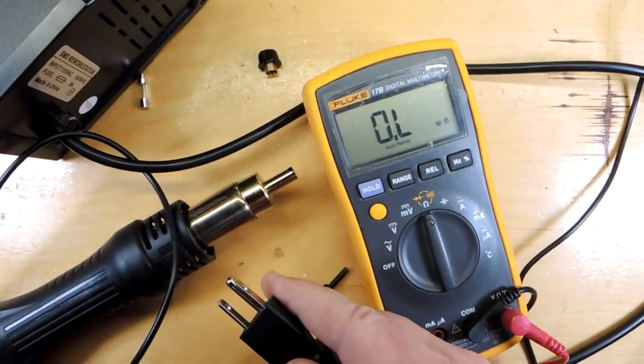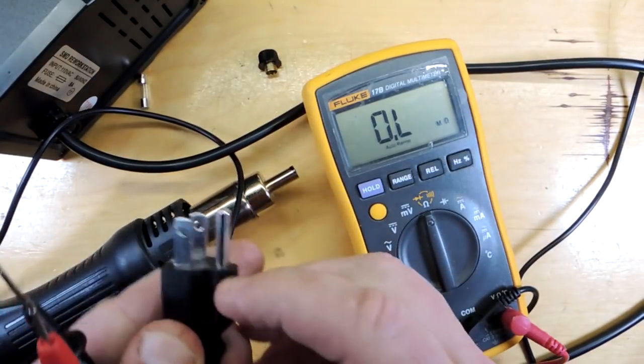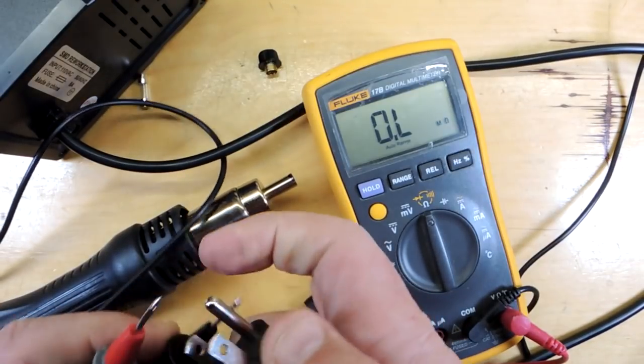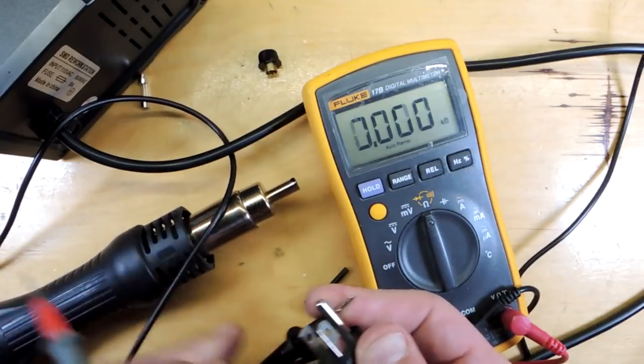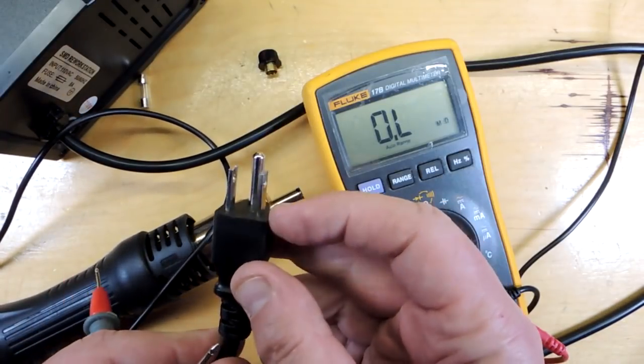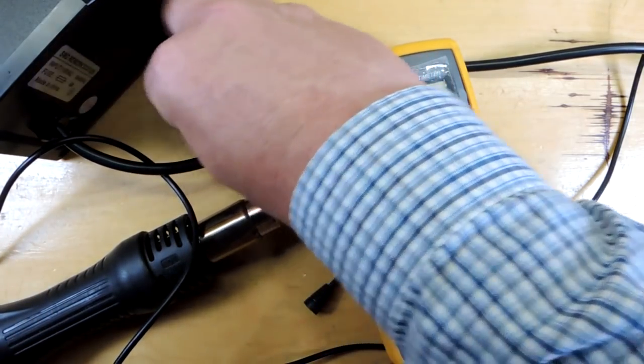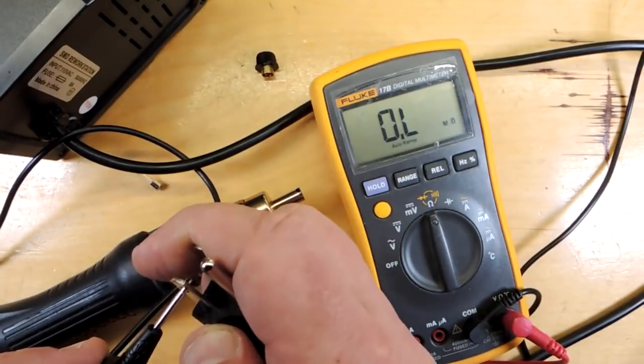Now let's do some basic electrical safety testing. I'm a North American, this is the North American plug. The chassis ground is here, I would hope that has that grounded. A quick check of continuity and sure enough this is the chassis ground. Now in my world the hot lead is on my right hand side. This unit has a fuse in it, you can see I've just taken it out, and the fuse should be on the hot side of the assembly.